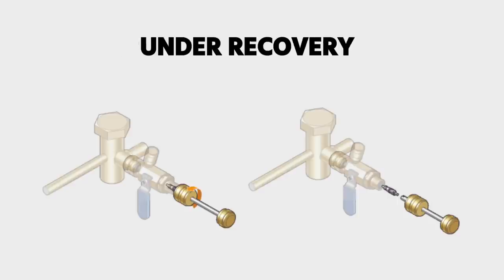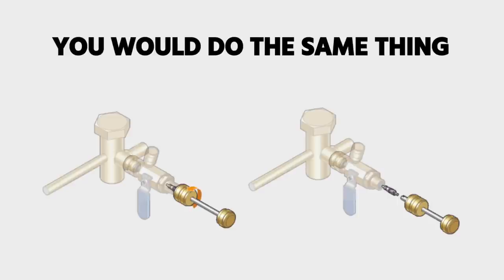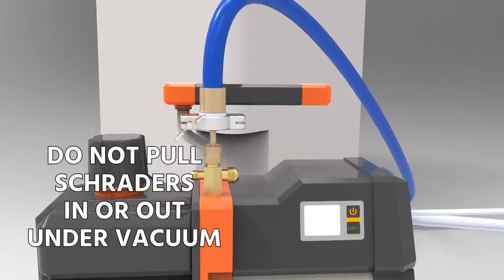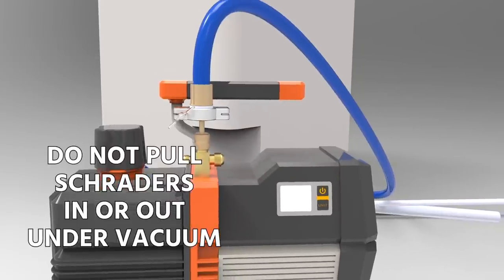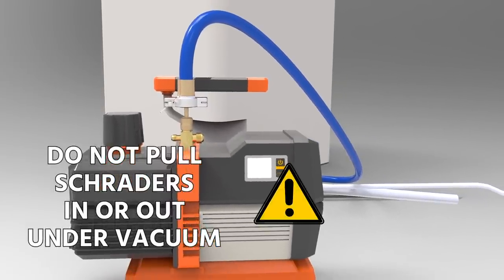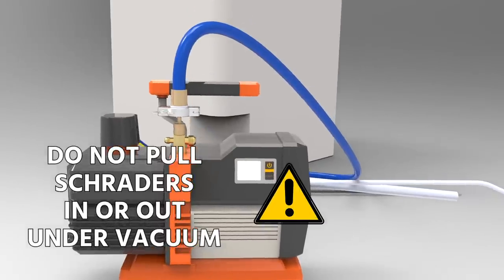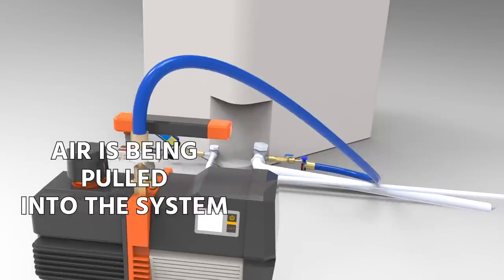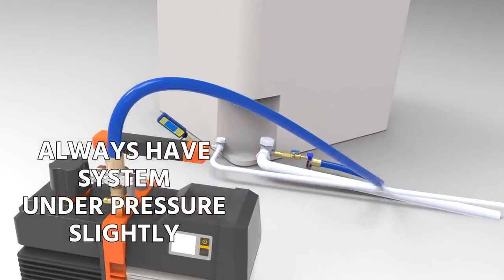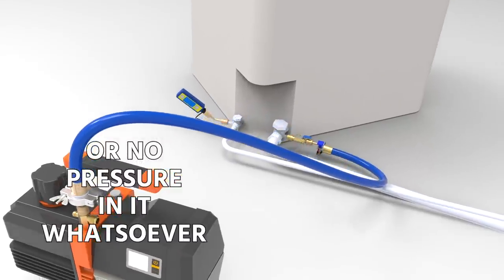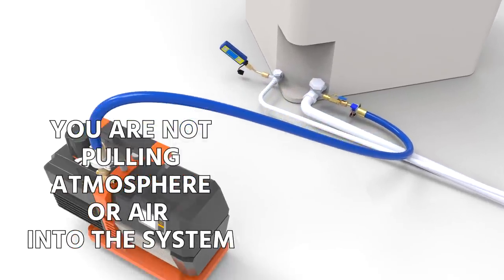Like I said, under recovery, you would do the same thing. You're going to recover refrigerant and pull it out for that purpose. One really key thing here is you do not want to pull Schraders in and out under vacuum. I'm going to say that again, do not pull Schraders in or out under vacuum because under vacuum, you will have some air that's pulled into the system, and we don't want that. You always want to have the system under pressure slightly when you do this or having no pressure in it whatsoever. That way you're not pulling atmosphere or air into the system.